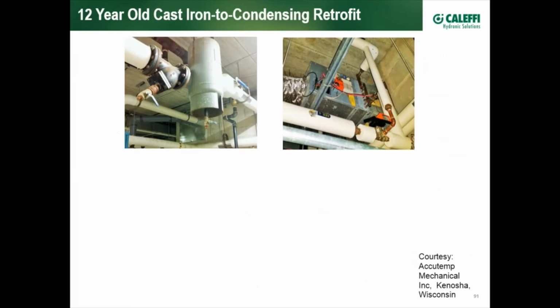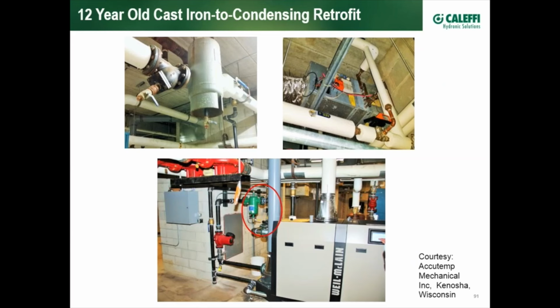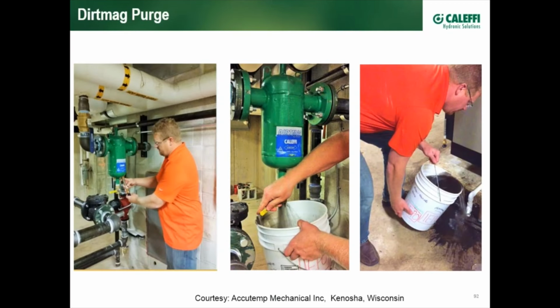A real job, a 12-year-old system that had a cast iron boiler. Problems incurred. The boiler was changed out, upgraded to a high-efficiency condensing boiler. Problems continued on with the system. The contractor heard about Caleffi's magnetic dirt separator, used it as a tool to basically clean up the job. As it worked, the magnetite was caught, and over a few weeks, the contractor was able to clean up the system and now is running nicely.